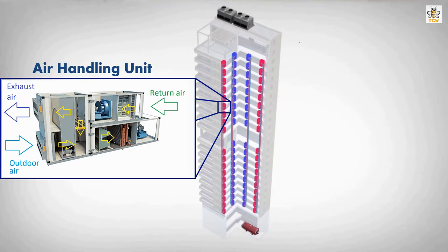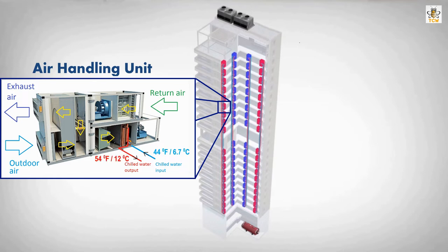The mixture of outdoor air and return air flows to the cooling coil. Low temperature water enters the cooling coil, absorbs heat from the air, and becomes hotter. This cooling water is called chilled water. The chilled water temperature is 44 degrees Fahrenheit or 6.7 degrees Celsius, and after absorbing heat from the air, it rises to 54 degrees Fahrenheit or 12 degrees Celsius.